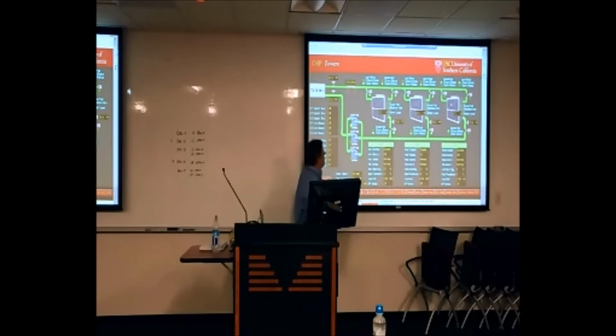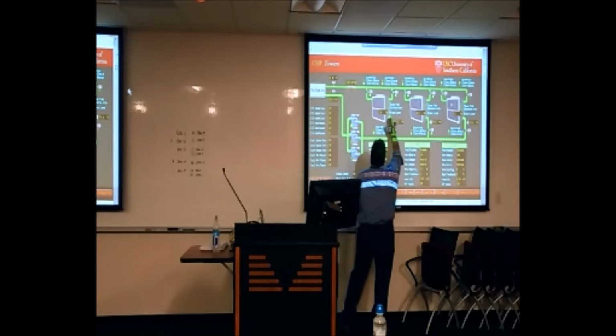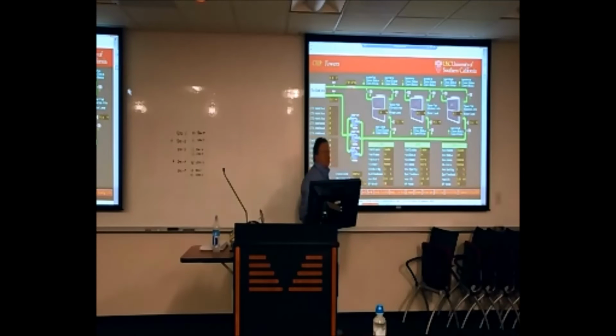over to the next. Also indicated on each tower is a water level. And this water level is located on the north side of the tower, and it's in a stilling well, which is right beside a stilling well for the mechanical float. So if you're on the north side of the tower looking at it, you'll see the stilling well for the mechanical float. It's in sort of a blue container, and you'll see the mechanism that goes up and down. Directly next to that is going to be the Honeywell stilling well with the Honeywell level sensor located right there. And it's clear tubing, so you can look in and see the level sensor actually traveling up and down.